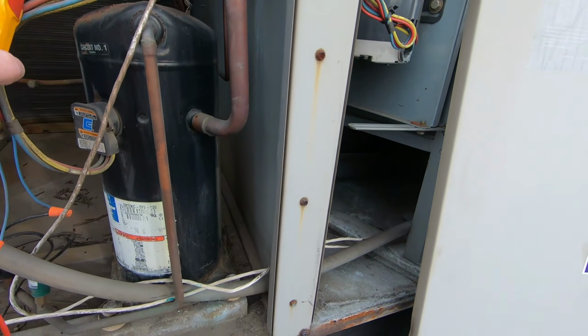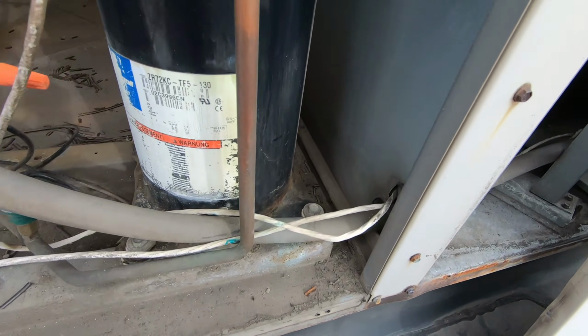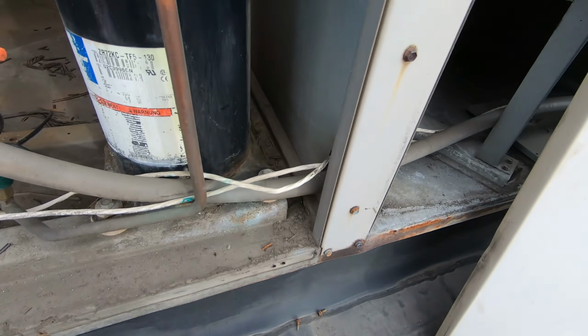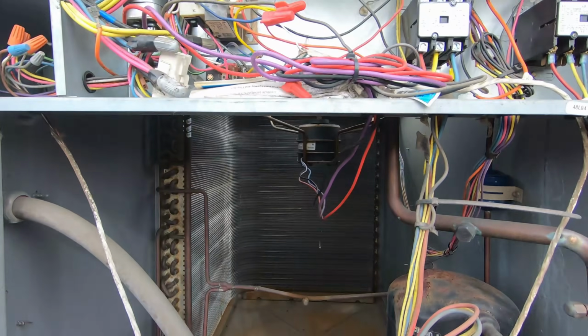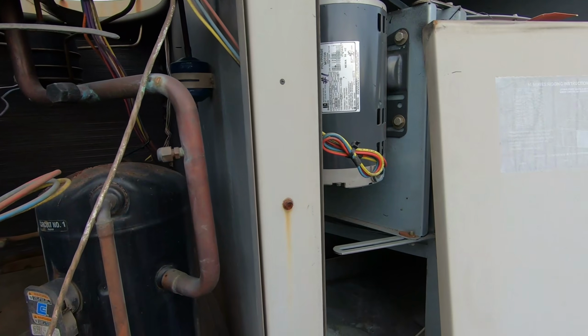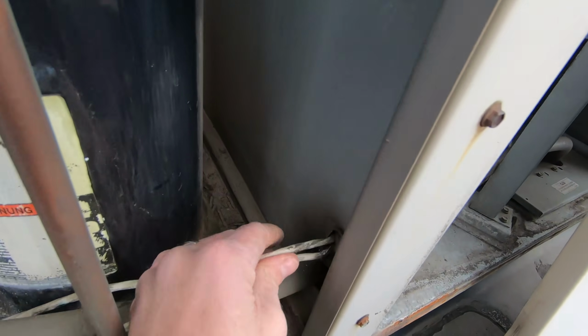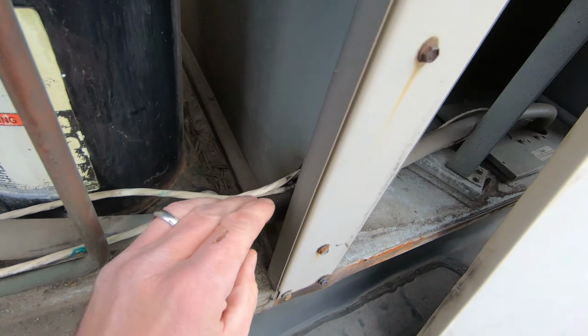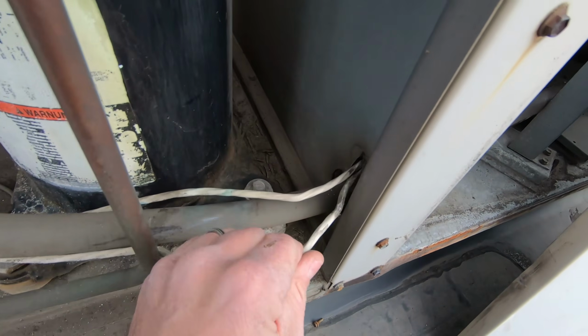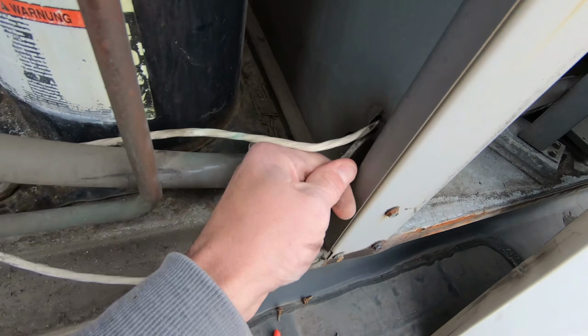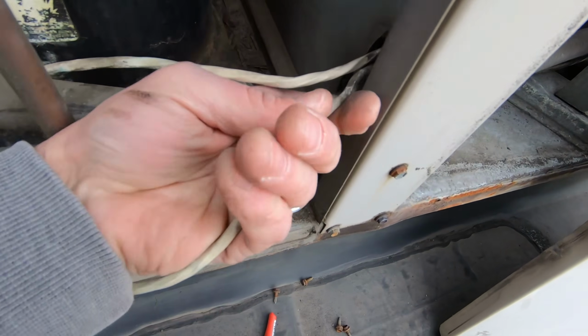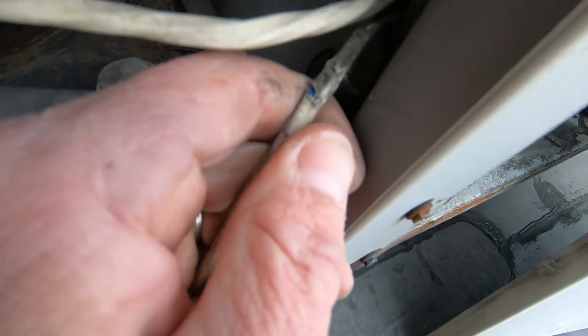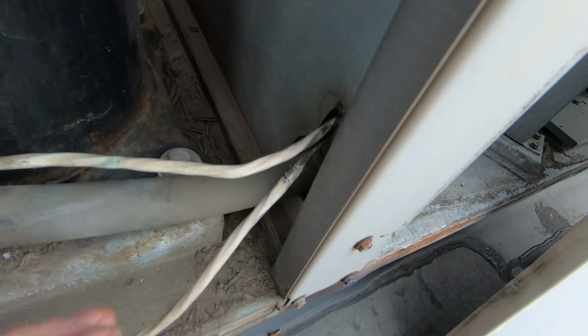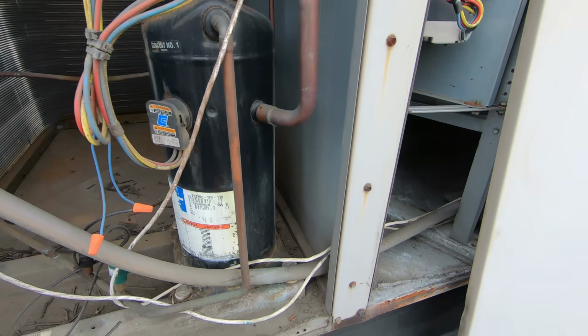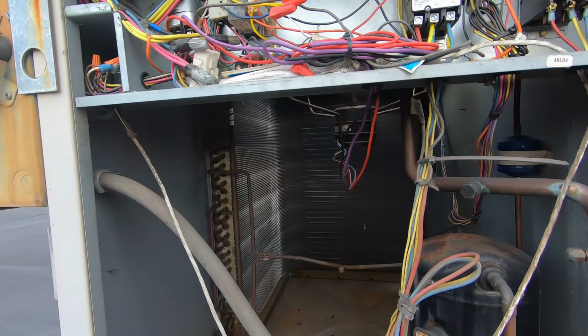The low volt thermostat wire running through here has a break in it, and that's what's tripping the 3 amp breaker. I like when I find them quickly, because I could have spent all day here. I'm gonna pull this wire out right there, let me get you a better view. See that? As soon as I touched that, it started going wonky on me and tripped the 3 amp fuse.